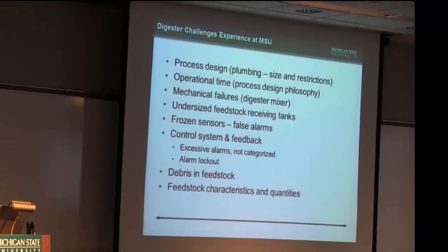Also struggling still with our operator time. Originally, the company that built this for us forecasted 1 hour a day to 2 hours a day of operator time. Through most of 2014, we were at 8 to 10 hours a day. We've done a lot of things over the past 3 or 4 months to improve operations and bring that operator time back down. We're comfortable that we can get it back down to 4 hours a day, which is actually what we had planned for. So we're getting close to that.